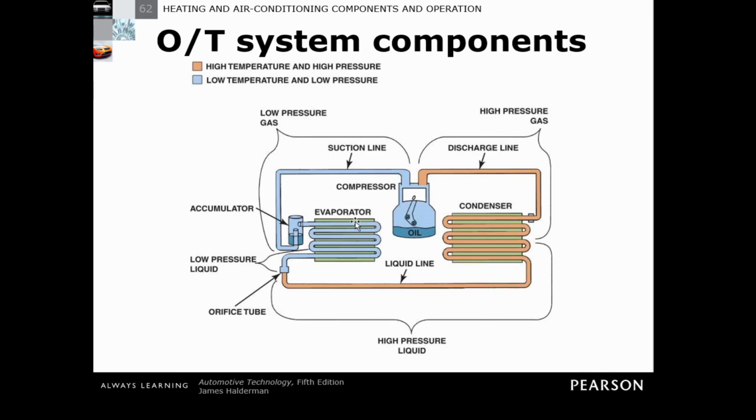Now, in an ideal world, we will have nothing but gas reach the accumulator, but all things being equal, it's never completely perfect. So we might still have some unboiled Freon over here. The accumulator acts like a reservoir for that and ensures that only low pressure gas is going to reach the compressor. So we make sure the system is going to work properly, okay?